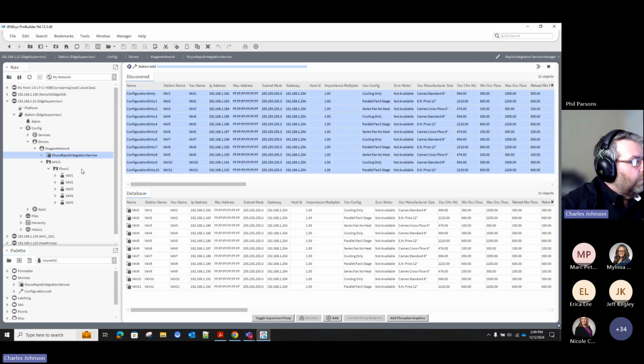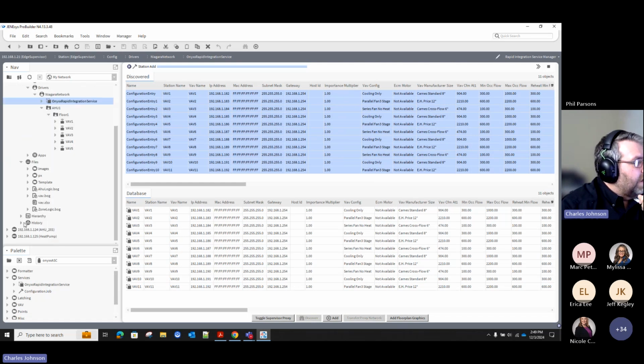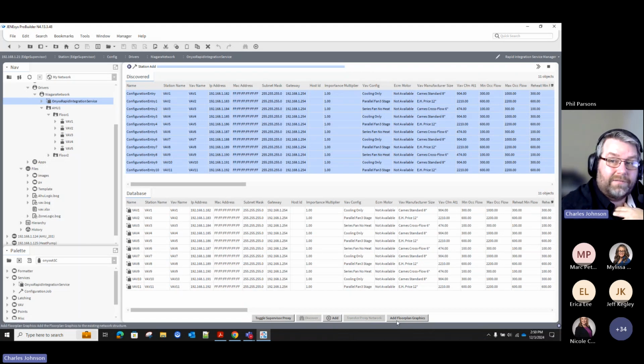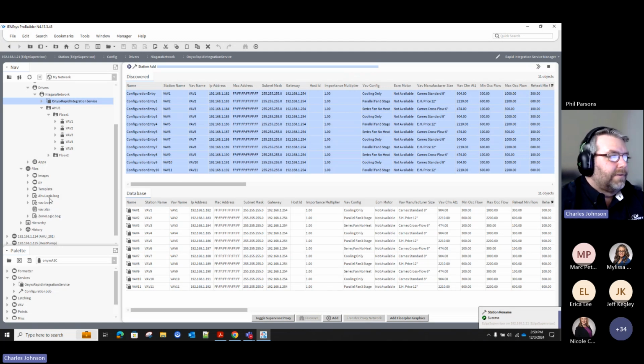Once we create both of the zones here, there are a few additional steps we'll add. First, we'll make sure all our information is passed up to the supervisor by doing a synchronization. Then I'll show you how to add the floor plan graphics, and then how to add the logic links already done for you, for your trim and response, auto commissioning, etc.